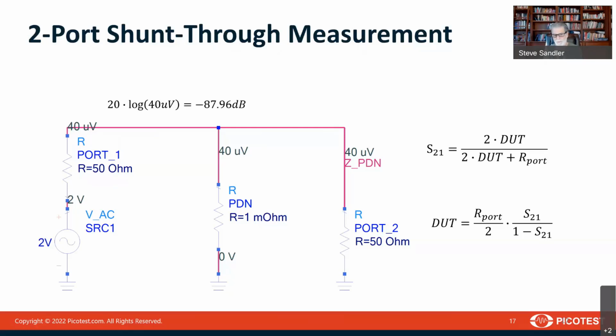If I connect the DUT between them, as I'm showing it here, a 1 milliohm resistor, for example, now we can see that the correct answer is 40 microvolts. Why do we need such large dynamic range? Well, you can see here that this measurement is a minus 88 dB measurement. So we need at least 88 dB dynamic range plus noise margin.